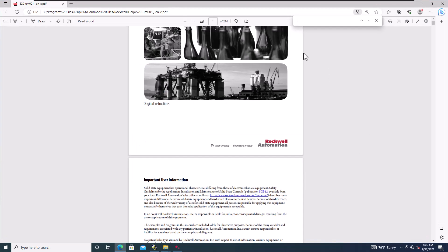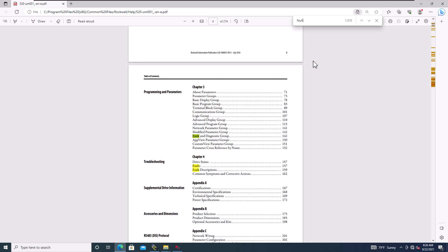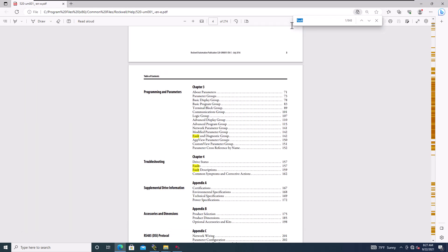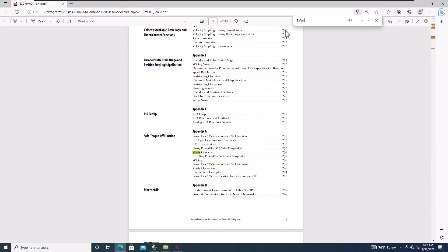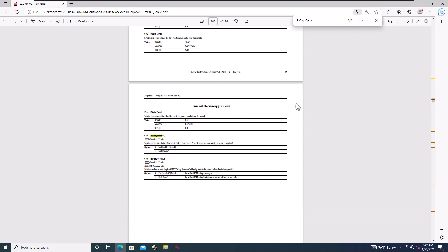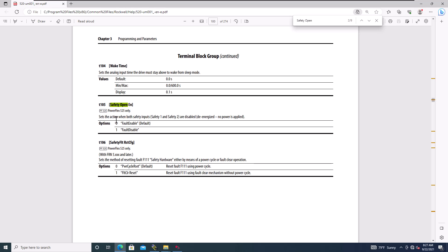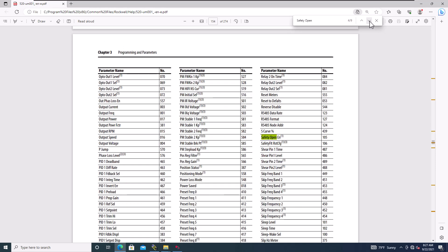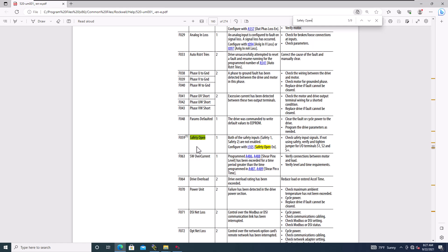We'll look at faults - you can look at the fault groups. Let's say we had an instance of a safety open, so we can just search 'safety open.' As long as you spell it correctly it will work. We'll see where that finds it - you can see right there are the parameters. We'll keep navigating down and we'll see that. You can see right here it's the safety open and they are enabled. We can come over here and look at this - this actually shows the fault.